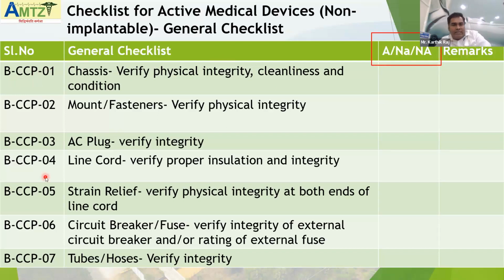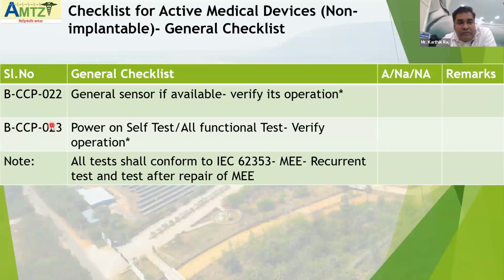So this is the general checklist. The general checklist has almost 23 points, plus one more thing: all tests shall conform to the IEC 62353 standard, which defines the requirements for electrical safety testing. ME means medical electrical equipment: recurrent test, and test after repair of medical electrical equipment.